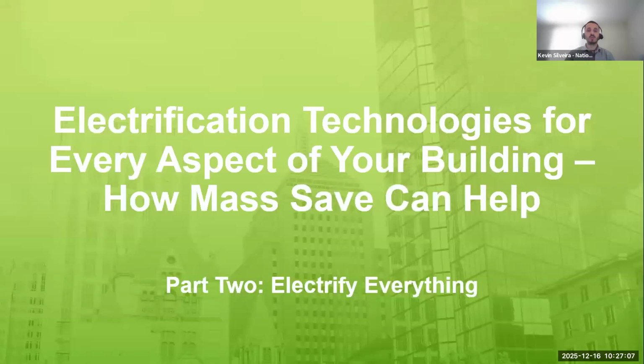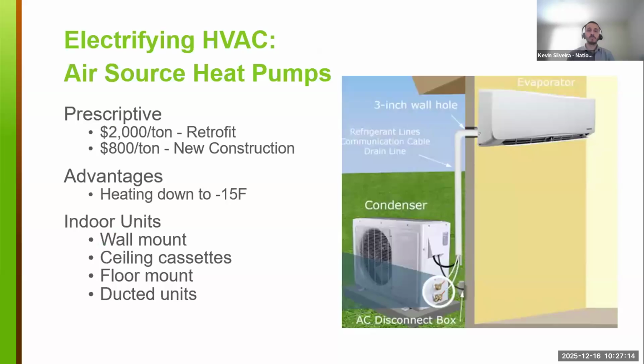And with that, I will kick it over to Greg to discuss the electrification options for a building. Sure, thanks, Kevin. So this might be the category of heat pump equipment most folks are familiar with and have seen at their homes: air source or split type air source heat pumps. They're pretty standard. You have your outdoor condenser, that would be your outdoor unit, and then your indoor units could be a wall mounted head, such as in this photo here.